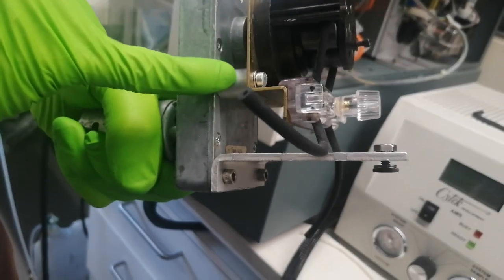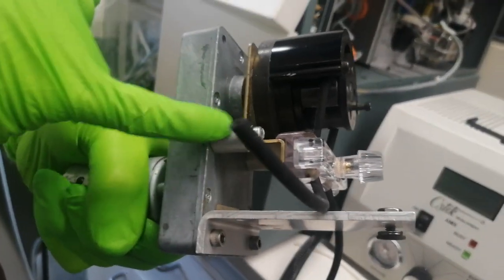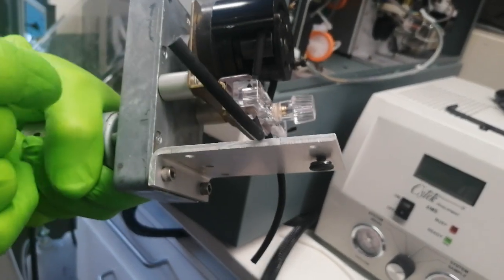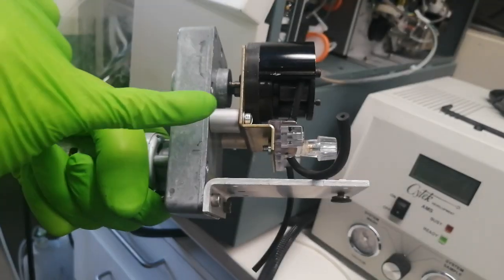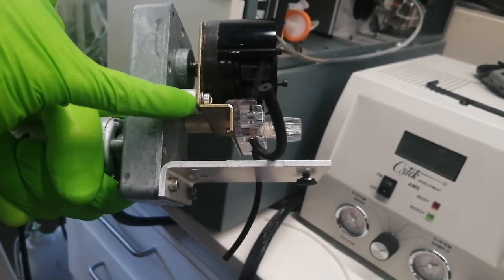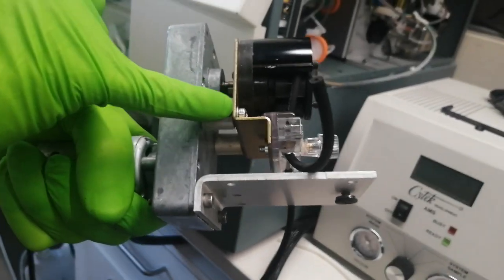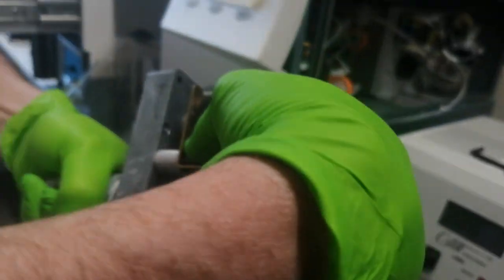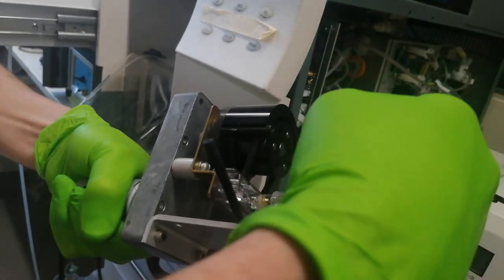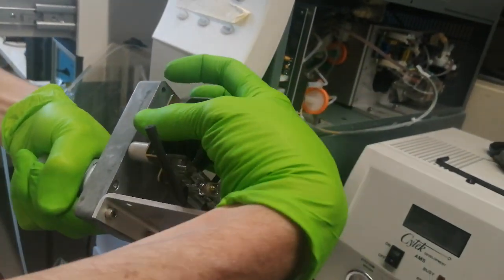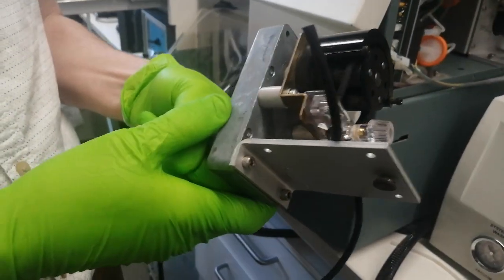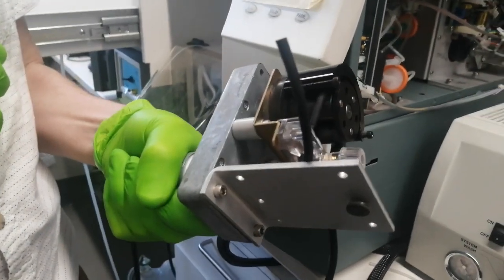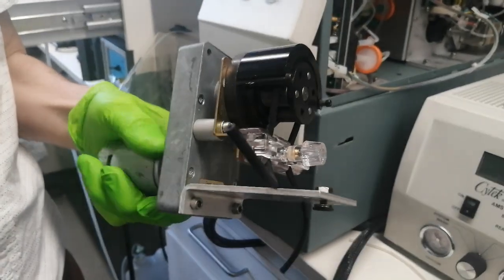Then this is the really fiddly bit. These spacers fall out. So when you take them off, these things fall off, and it's a pain. But the best thing to do is to put a little bit of tape or something on this side, or just anything, glue even, and just stick it on there. Put it in place, get it slightly engaged, have it turning as you tighten it up. So open the tube, as you tighten these screws, have the tube open and have the thing actually turning as you tighten it into place. Otherwise it might be at a slight angle when you try and do it, and it will make a horrible noise forever.